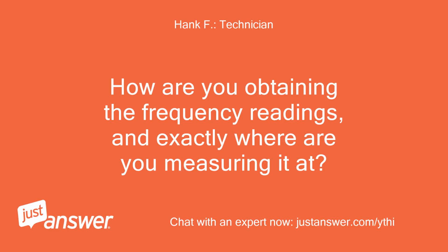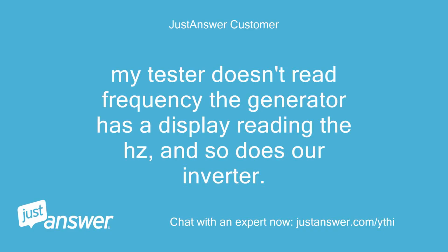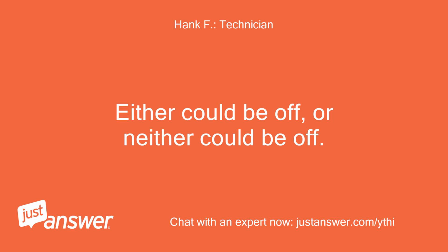How are you obtaining the frequency readings, and exactly where are you measuring it at? My tester doesn't read frequency. The generator has a display reading the Hz, and so does our inverter. Either could be off, or neither could be off.